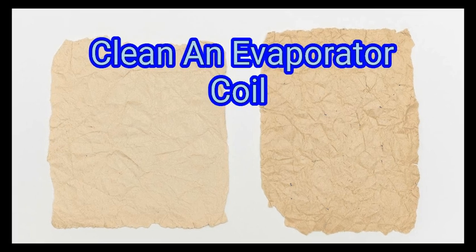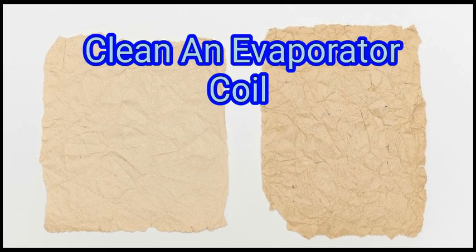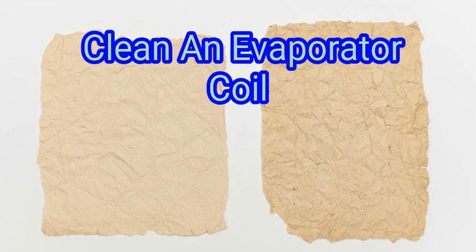Air blowing across the coils in your air conditioning system can cause dust and other debris to stick to the coils. Systems with dirty coils use more energy than those with clean coils and cool spaces less efficiently. By annually cleaning the evaporator coils of air handling units before the cooling season starts, you can increase your AC system's cooling efficiency and overall life expectancy.